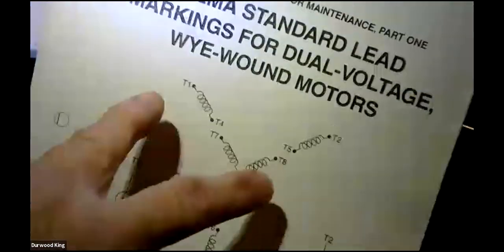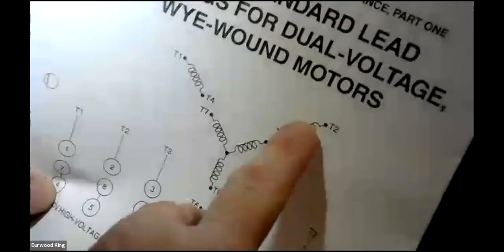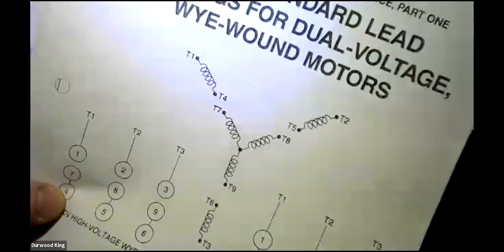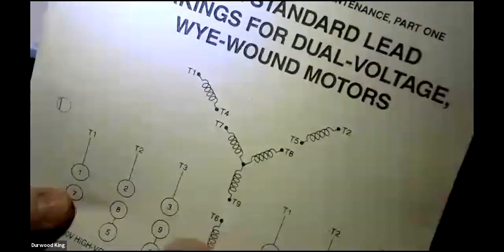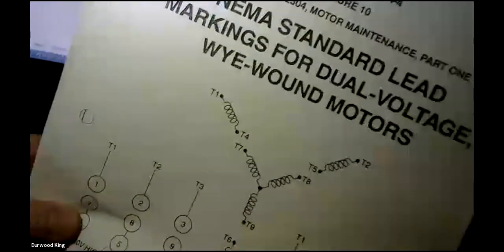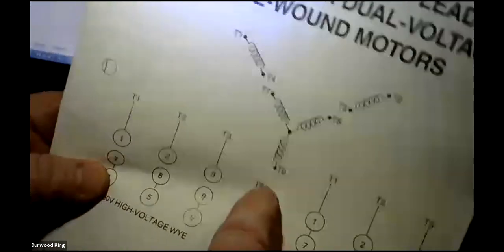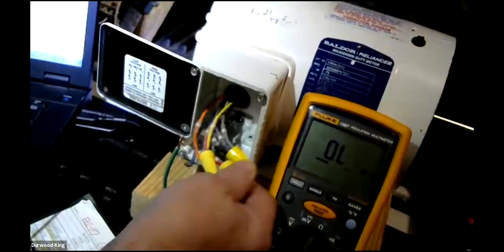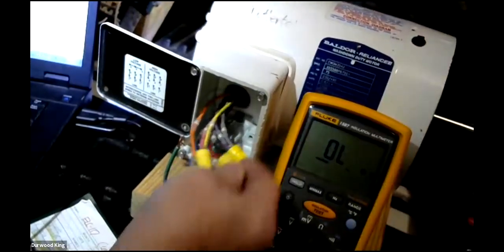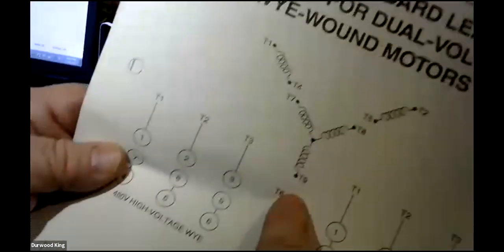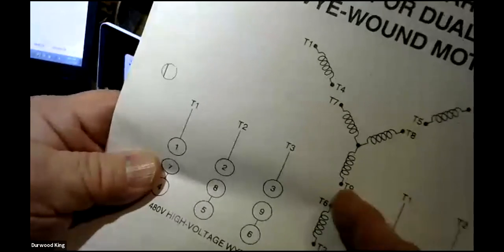But next month you see 20 and 30 and 20. Something's wrong. The next month you get 20 and 40 and 20. So guess what? Something's happening down in here. You need to check your wire nut that's in here and make sure it's okay, because your wire nut may be an issue. You may have corrosion in there, or you may have oxidation in that wire nut causing that resistance to be high. If you take it apart and redo it, and you still have a high resistance going this way, but balanced readings that way, there's something going on.